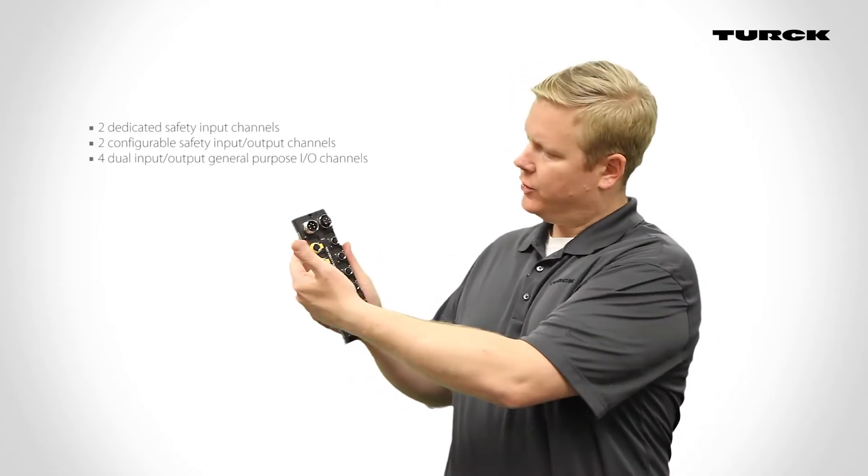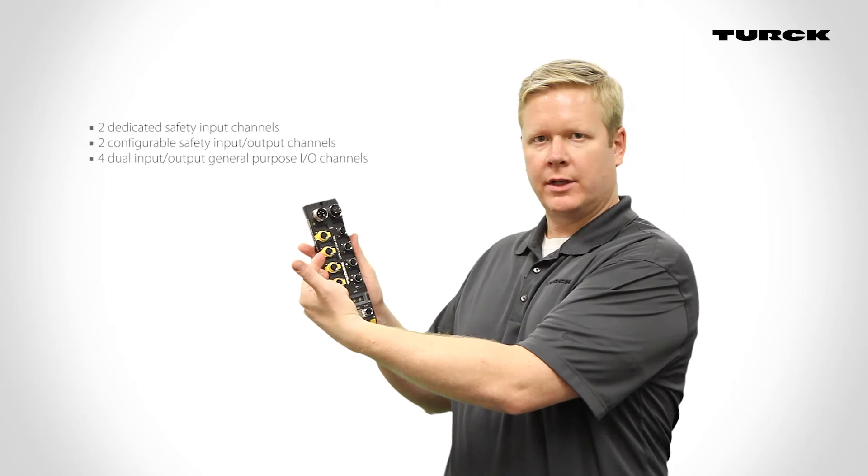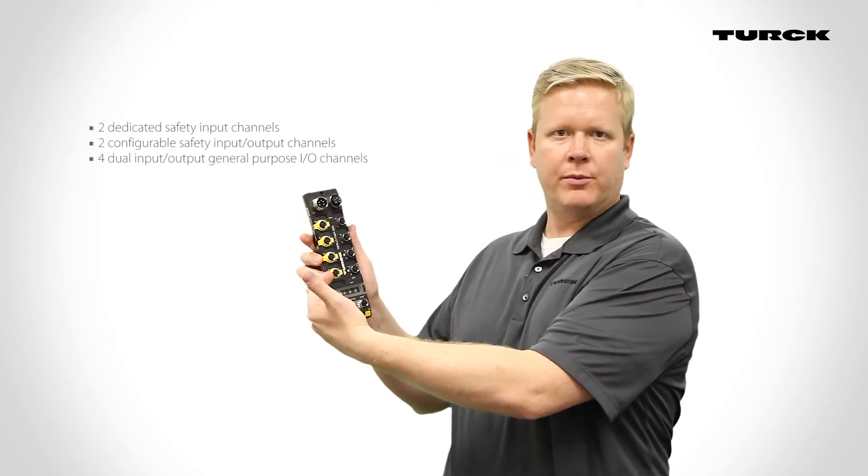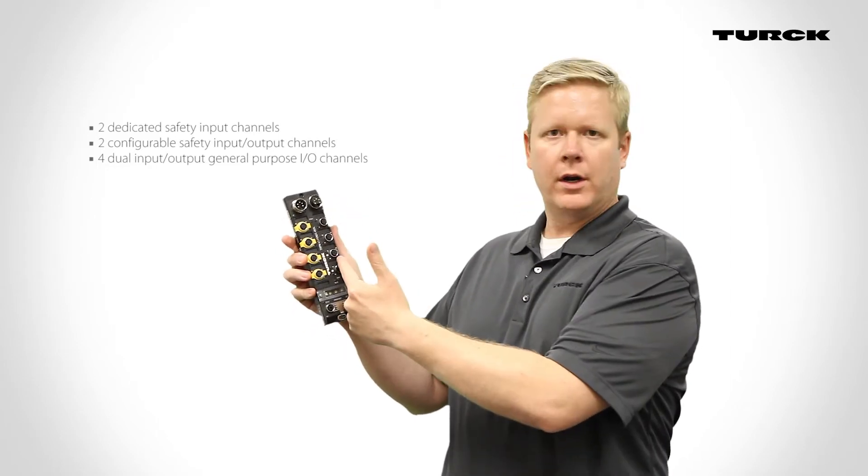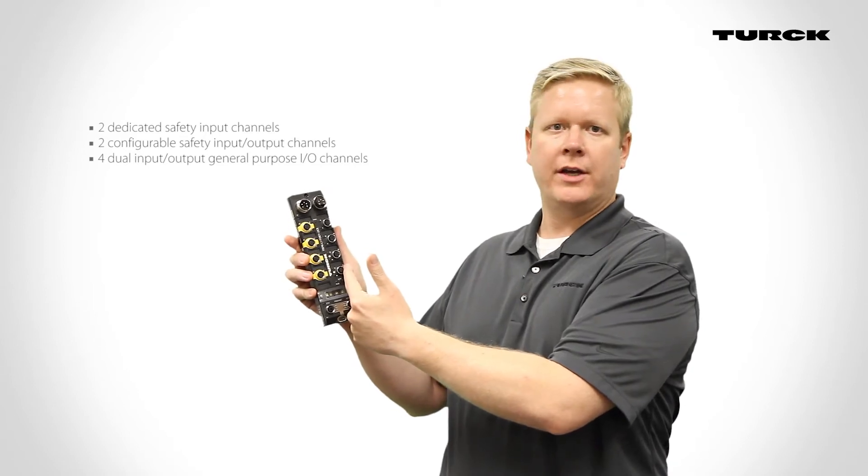This TBPN module features up to IP69K protection, which allows for mounting directly onto the machine. It has two dedicated safety input channels, two configurable safety input-output channels, and four dual input-output general purpose I.O. channels.